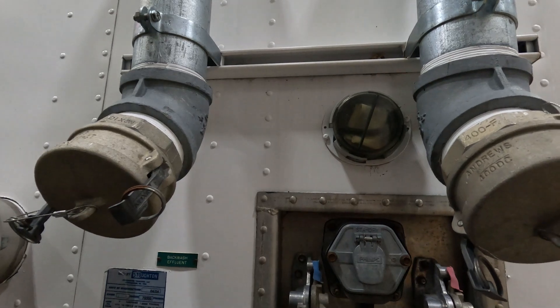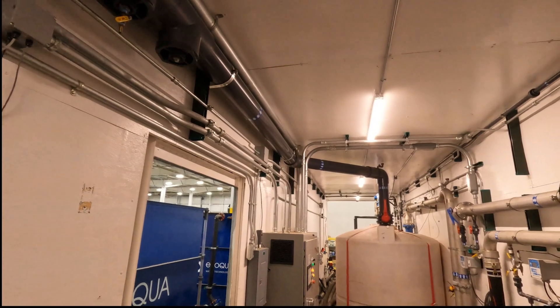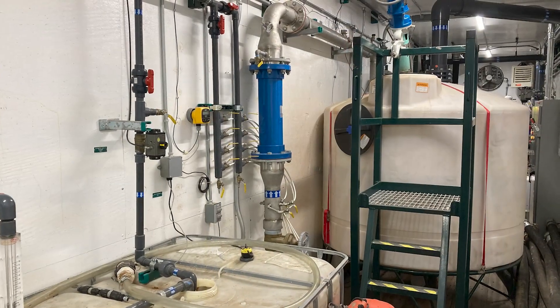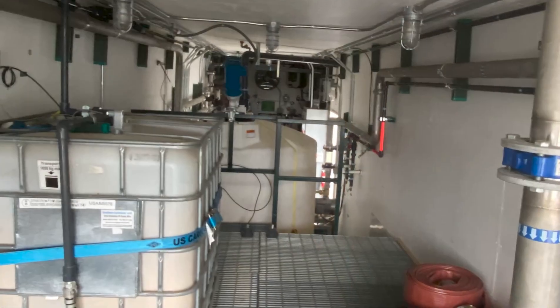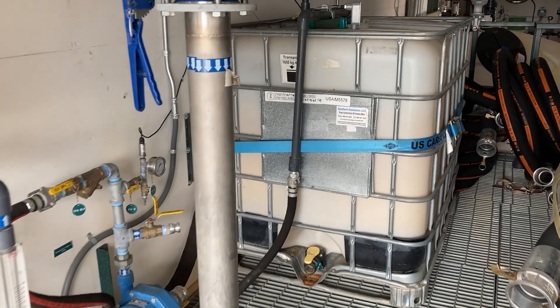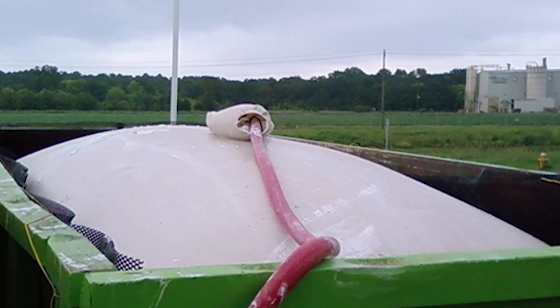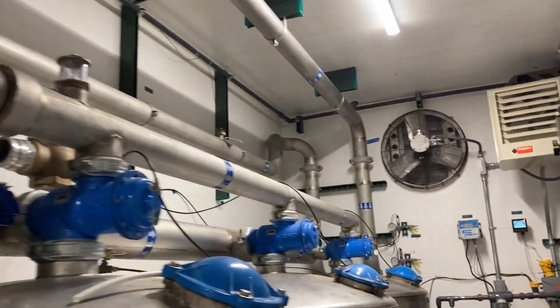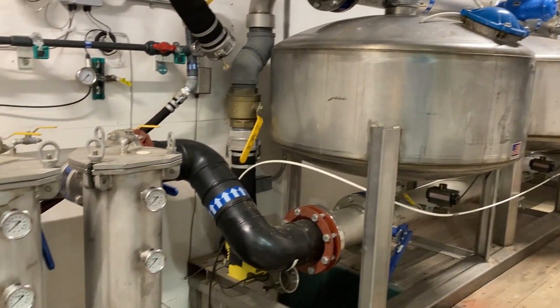The influent routed through the system flows into the poly tank where its pH is measured again and mixed with polymer. Contact time is provided to achieve the necessary pH adjustment. To settle the heavy solids, the effluent moves to a geotube. Depending on the application, the geotube may either be inside the SRS or connected externally. After further solid settling, the effluent flows from the geotube through a series of sand filters followed by a set of bag filters, which achieves the final turbidity set point as monitored by on-site controls.